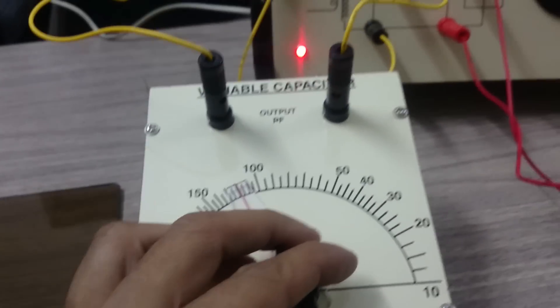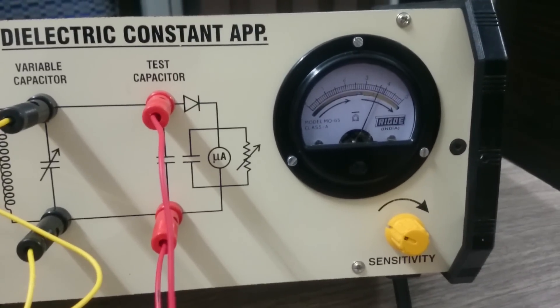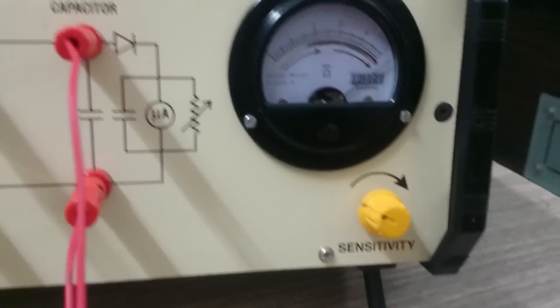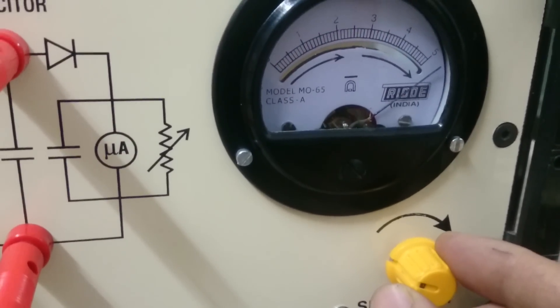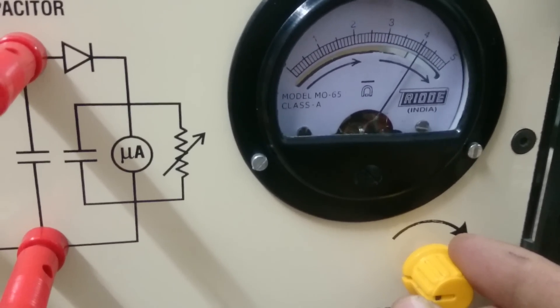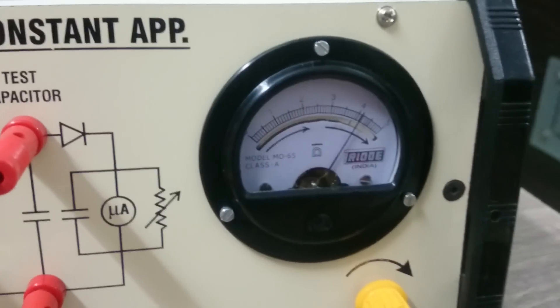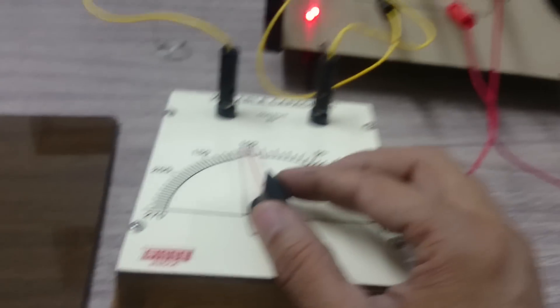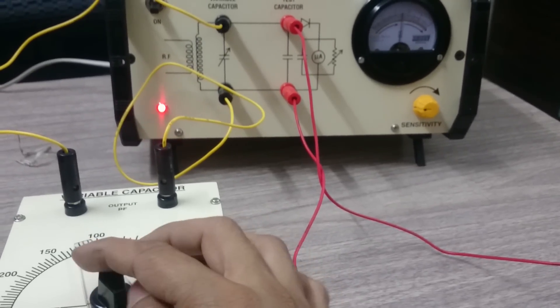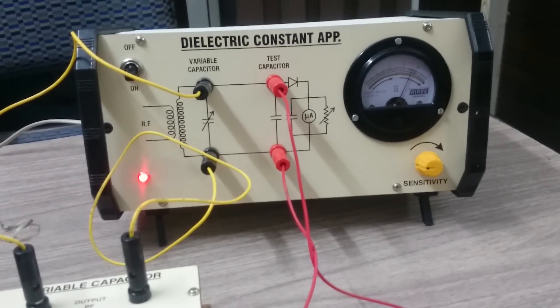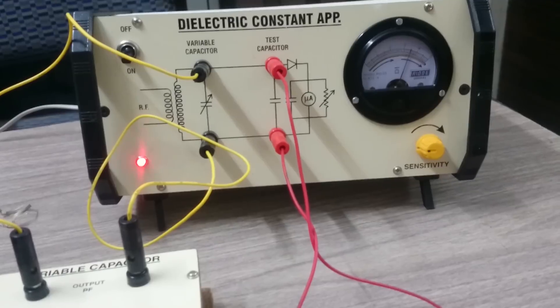With respect to this variable gang capacitor, by rotating you can see the reading. It is going beyond the scale, so by rotating this sensitivity knob, keep it inside the scale. It should be near about four or four and a half. Check that reading again. It should not go beyond the scale. It is within the range.